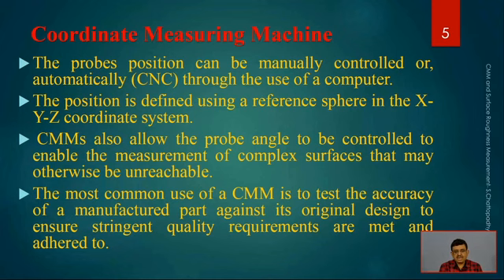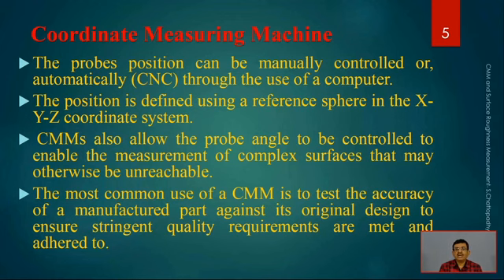The probe's position can be manually controlled via a joystick — one can move the probe from here to there, just like a game — or it can be controlled by computer, which senses where positions are and where data needs to be captured. The position is defined by a reference sphere in XYZ coordinates — mainly Cartesian, but easily convertible to cylindrical and spherical coordinates. CMMs also allow the probe angle to be controlled to enable measurement of complex surfaces that may otherwise be unreachable or inaccessible.